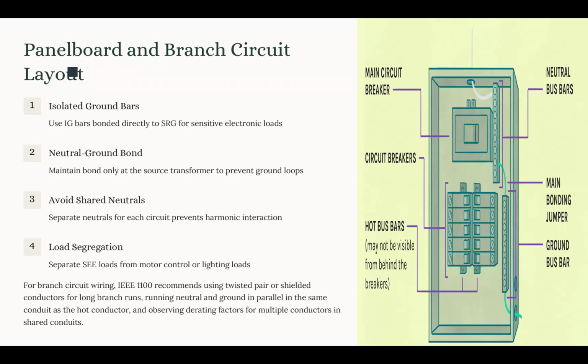Why do we have this recommendation? We need that to stabilize the ground reference for sensitive equipment by avoiding noise coupling from the building structure ground and providing a low impedance, we said less than 1 ohm, for high frequency transients. So each panel serving those sensitive equipment should have an isolated ground bar bonded directly to the SRG. It should not be connected to the conduit or building steel. Directly to the SRG is the path for those bars.